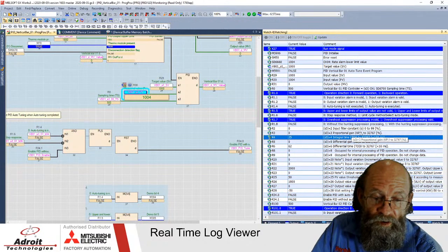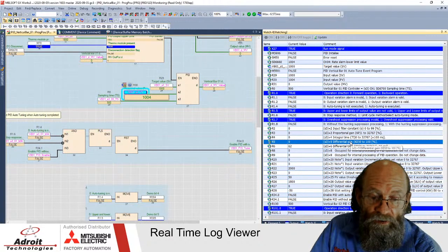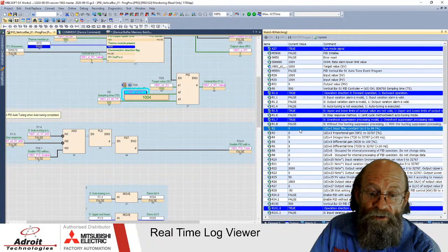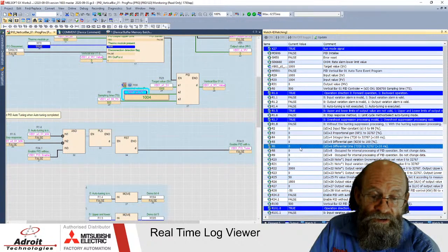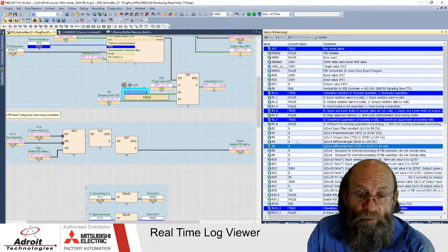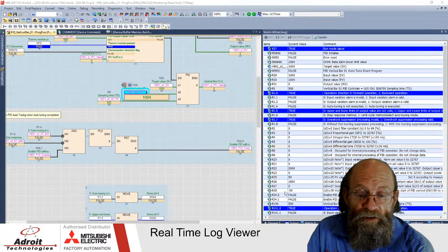So that was my proportional gain, and this is my integral time. I'm making them all zero. My differential gain is zero, and my differential time also is zero. These are the values that I don't know, on how my temperature sensor works or how my PID would heat my element. So the PID will do a quick test on the element by pushing it over a certain limit.